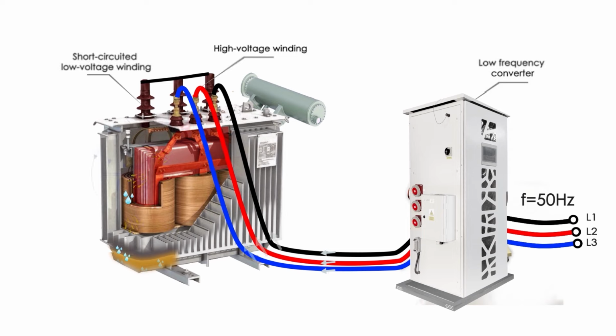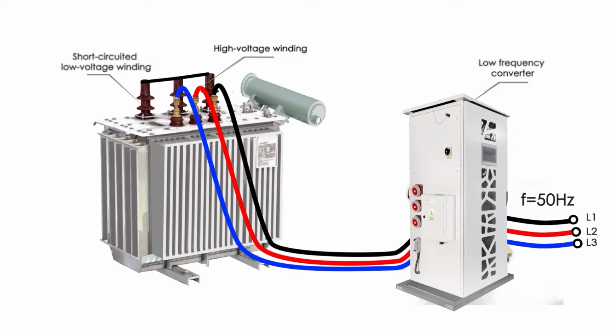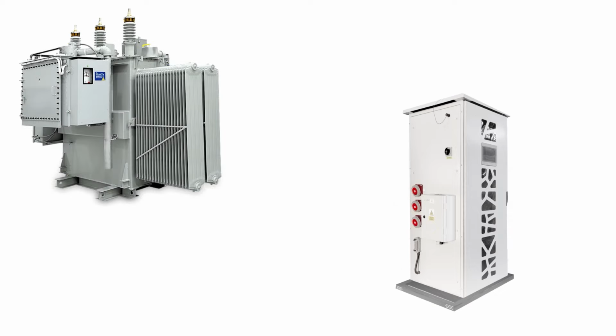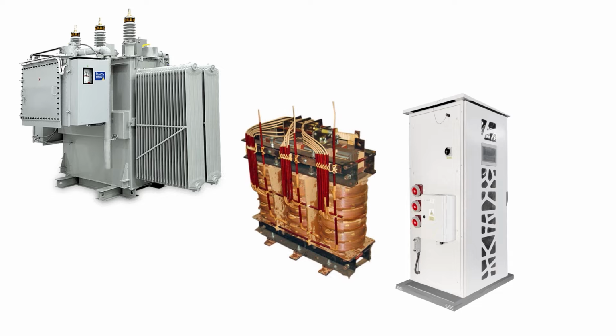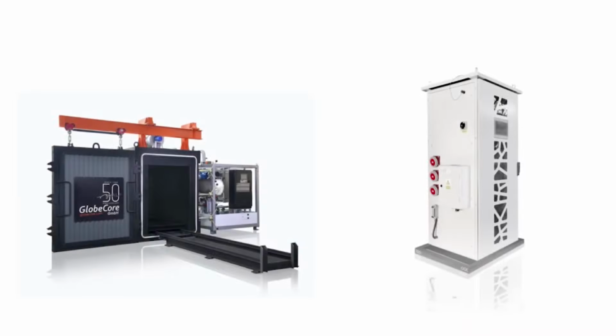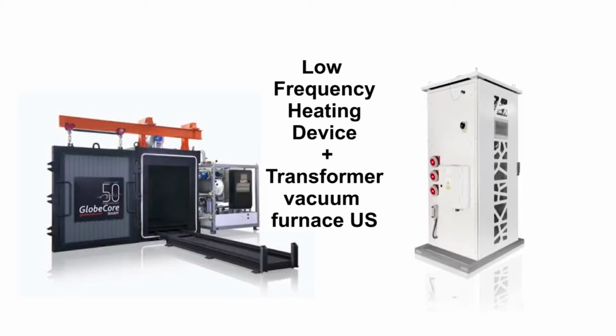The low-frequency heating method can be used both for drying new windings before they are installed into the transformer, and also for drying windings of aged transformers. When drying new windings, the low-frequency heating method can be used in conjunction with vacuum chambers to improve efficiency. In this case, low-frequency currents warm the windings up well, and the released water in the form of steam is removed from the chamber due to evacuation.